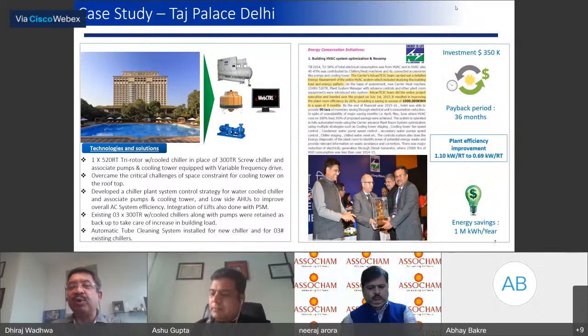All these strategies together helped the customer bring down energy consumption from 1.1 kilowatt per ton of refrigeration to 0.69 kilowatt. That's the power of what we can do inside a plant room today in terms of reducing energy consumption.